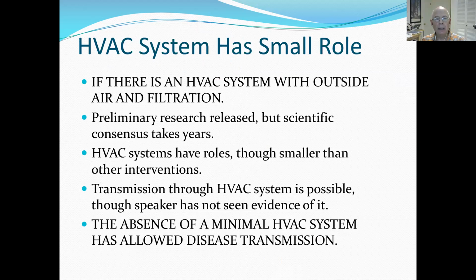So, you know, the HVAC system, if you have one, and if it's got a decent amount of outdoor air dilution ventilation, and it's got decent filtration, and more about what that means later, then it's not likely that the HVAC system itself is going to pick up infectious disease in the return air, run it through the coils in the systems, dilute it with outdoor air, run it through filtration, and then deliver it to somebody and infect somebody. Not to say that this couldn't happen, but none of the recent studies have shown that this is a primary means of disease spread. It's really the absence of a system.